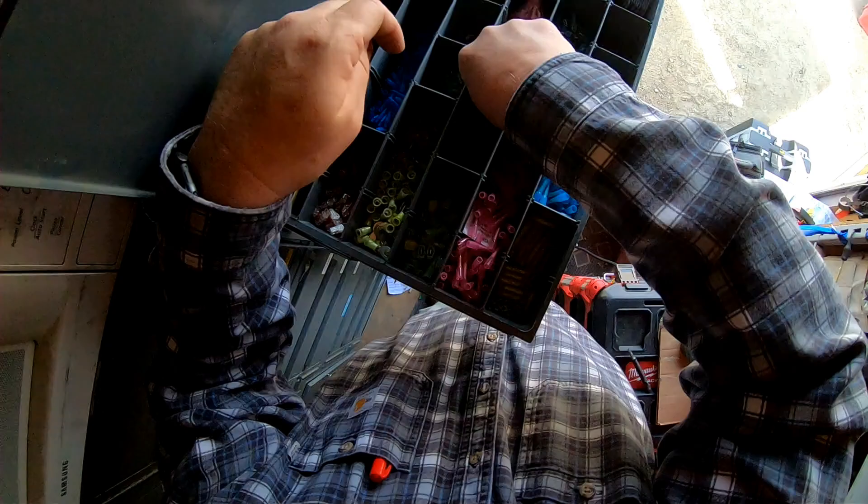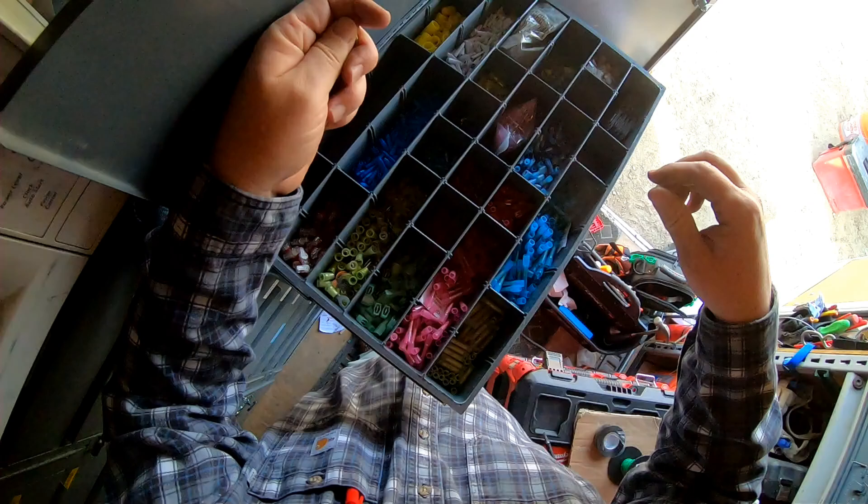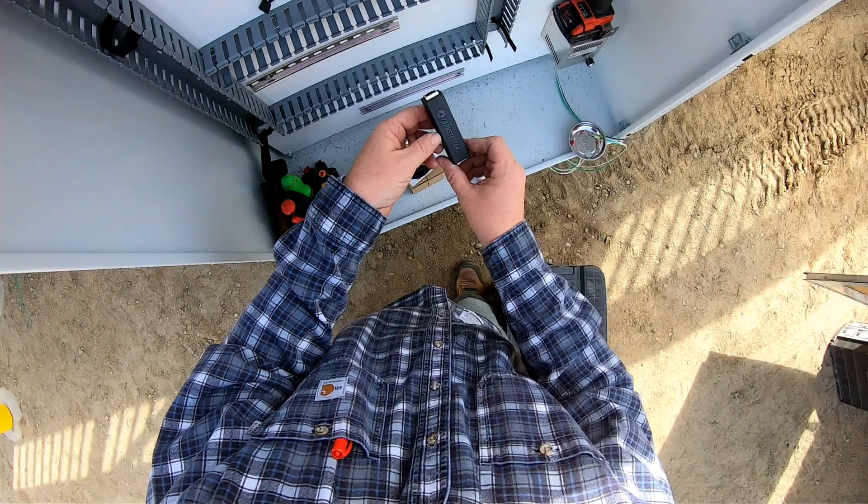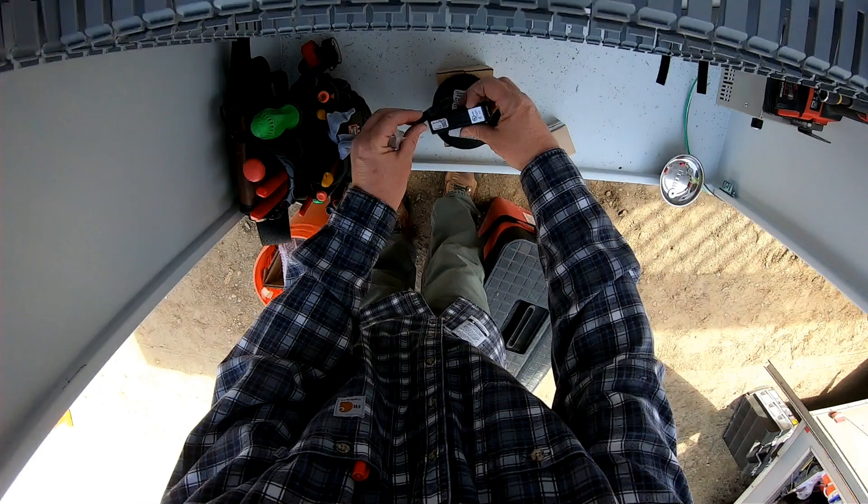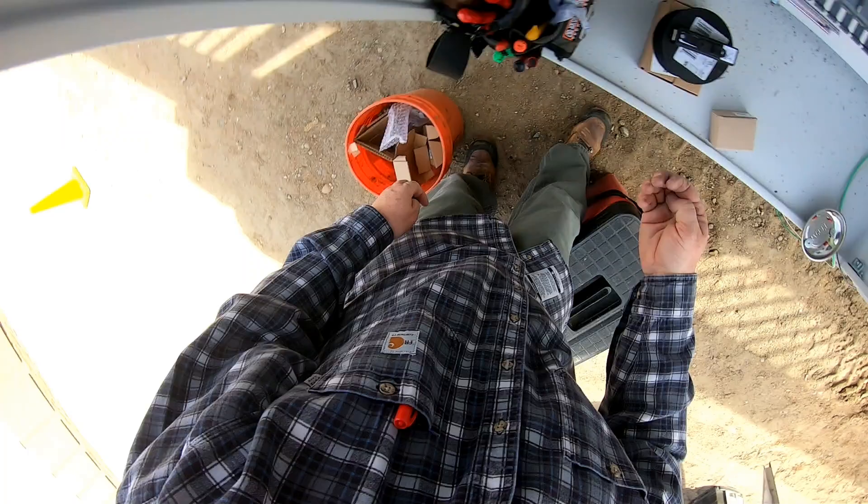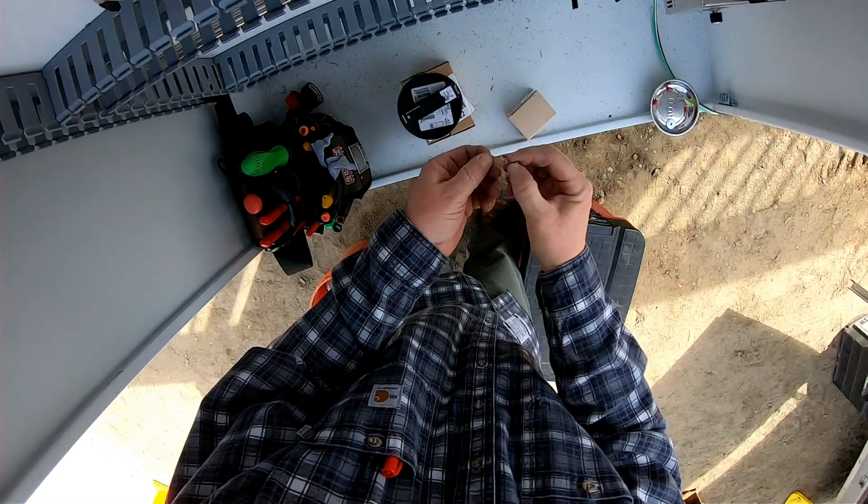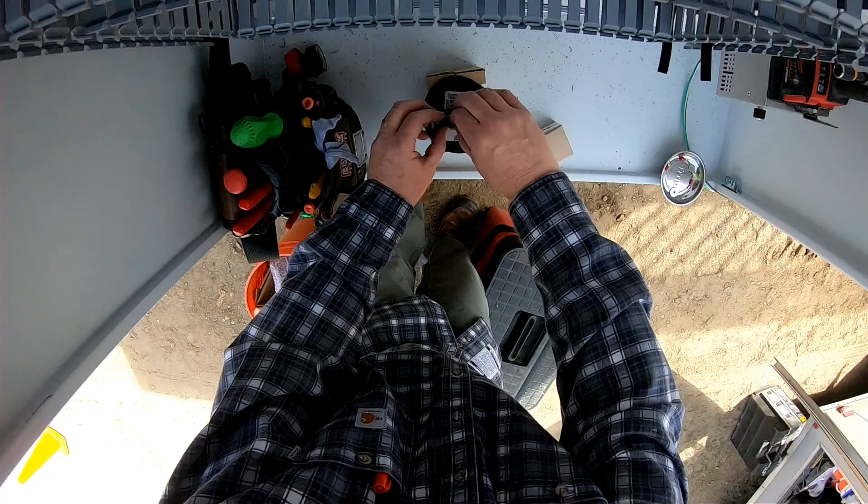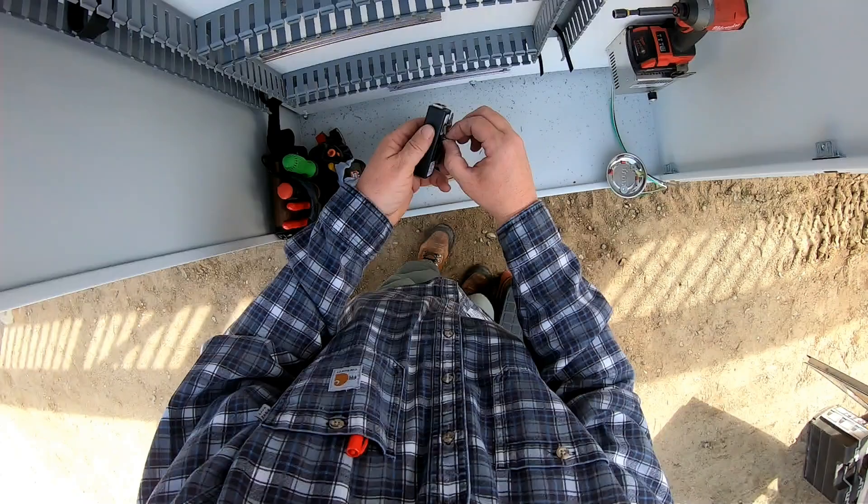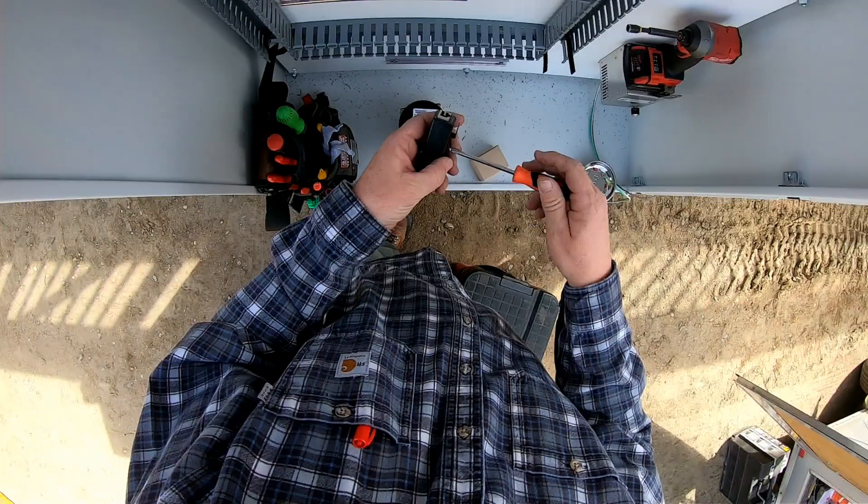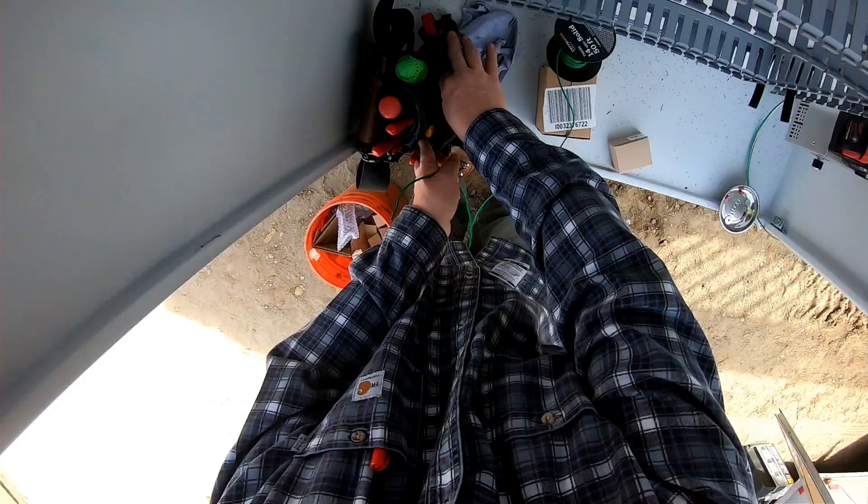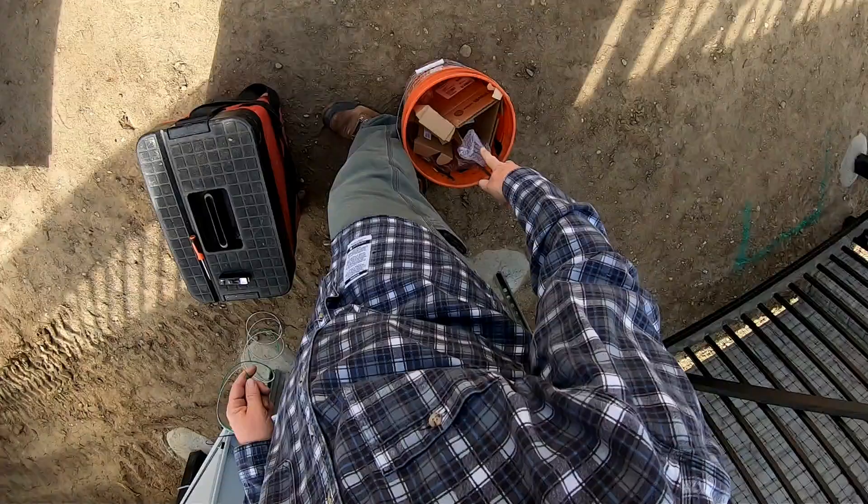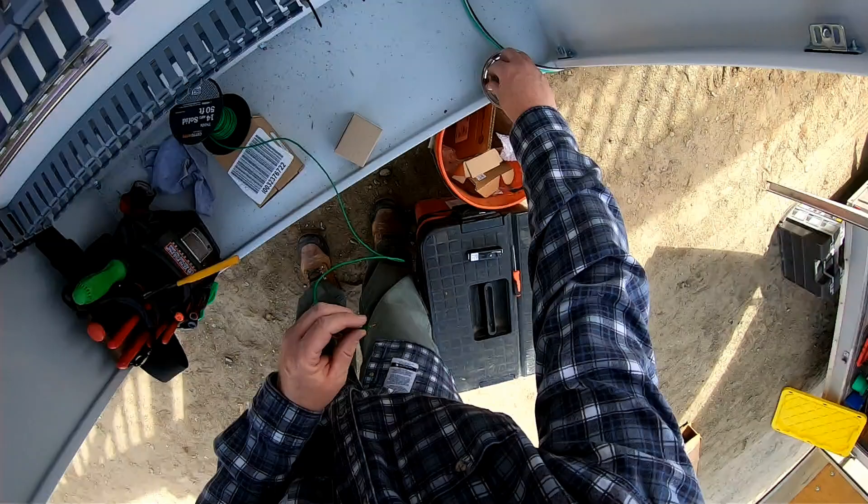Now I'm grabbing some ring terminals for my grounds. These are some little lightning suppressors, surge protectors if you will. Transtector is the model. I like to ground those each down to a ground bus at the bottom of the enclosure.